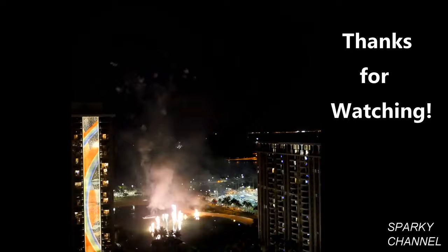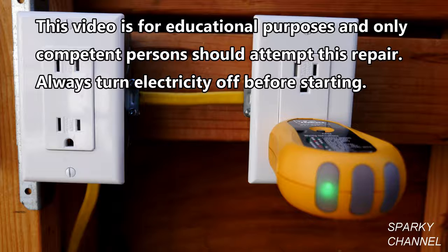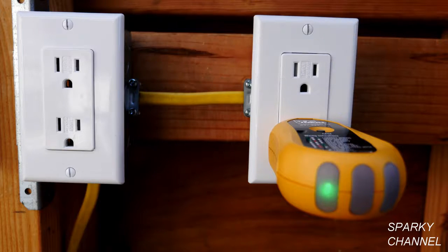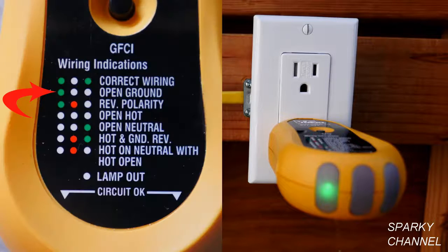Today I'm going to show you how to fix a receptacle that has an open ground. This means that this particular receptacle is not hooked up to the grounding system of the house. The first thing to do is plug an outlet tester into the receptacle and notice what light pattern you get. In this case we get one green light on the left and then 2 blanks. And if you look on the index, one green light on the left and 2 blank lights is open ground. This means that this receptacle isn't hooked up to the grounding system of the house.